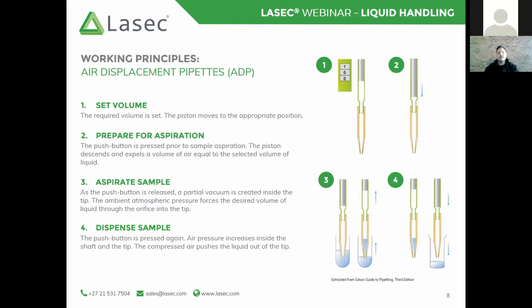This is going to be an important factor when we start discussing positive displacement and the limitations of air displacement pipettes. Another limitation that I would like to explain with an air displacement pipette right now is that we are working with an air gap or an air cushion. Air is subject to compression and expansion, so basically it's got elastic properties, all right? These elastic properties are relatively fine when we are aspirating aqueous solutions, things such as water or watery-based substances, but there are a lot of limitations when it comes to things that are more viscous. Unfortunately, the elasticity of the air inside the pipette doesn't provide a strong enough force for difficult or non-aqueous solutions. All right.